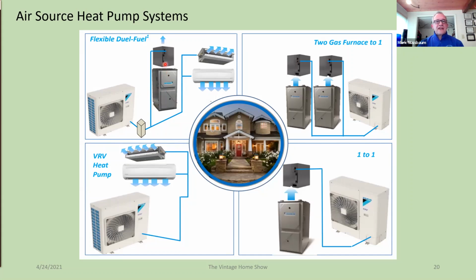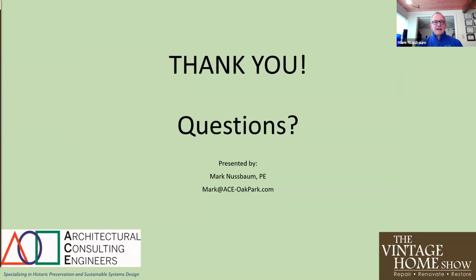Here's a furnace and coil, so I've got a gas-fired unit with a cooling coil stacked on top that hooks to this, and I'm also hooked to a couple of other fan coil style units that deliver cooling directly. Here I've got two furnaces. Here I've got a one-to-one furnace. Here I've got some air conditioning stuff. So it's just a really flexible system to install. It's very efficient. And as long as you make sure that you're covered for extreme low temperatures primarily, they're a very effective and lower cost alternative to geo. And a lot of these high efficiency systems have tax credits currently with the federal government, and some rebates also, that help reduce the overall cost. And that's all I got.